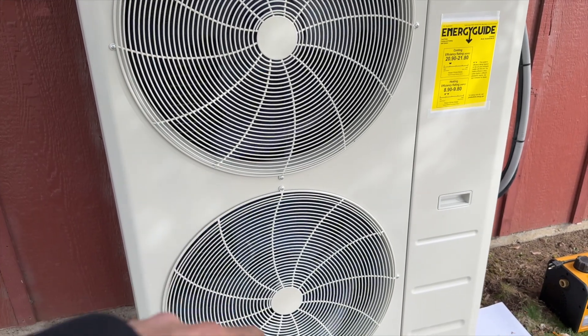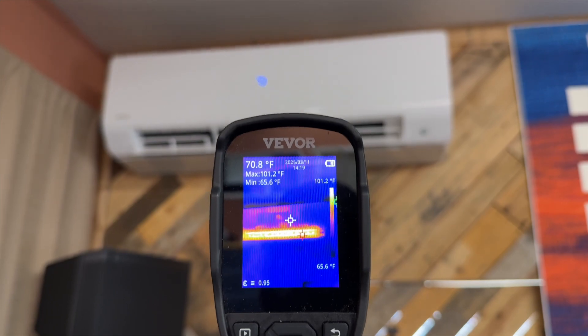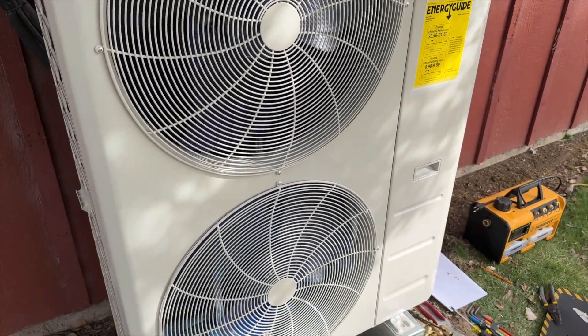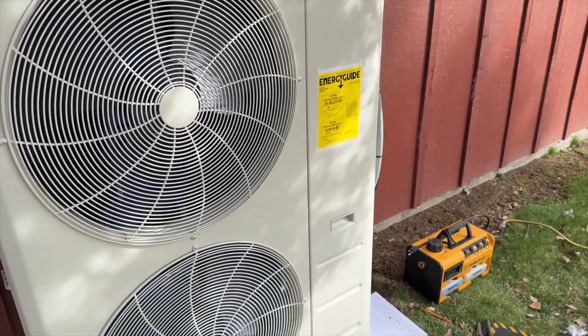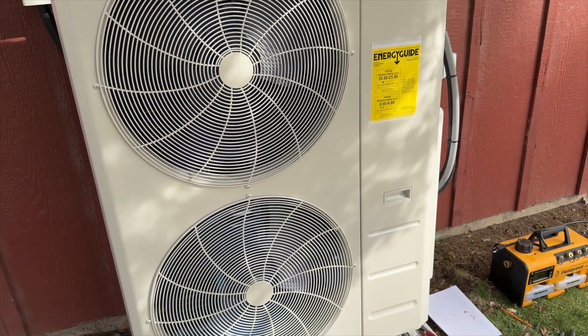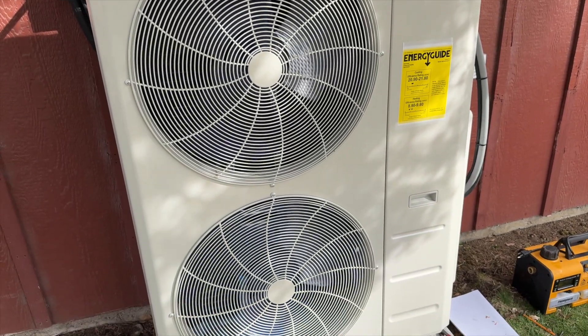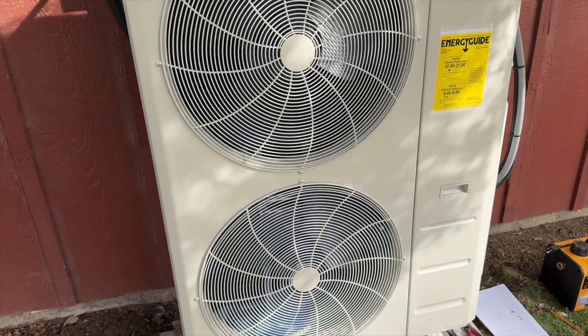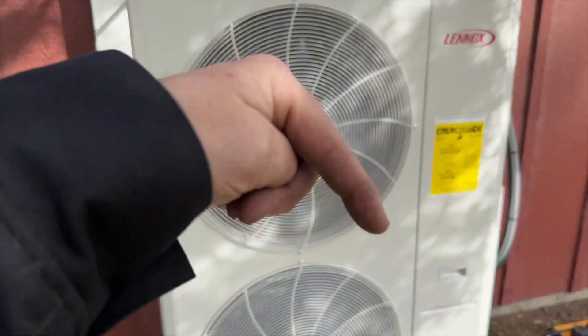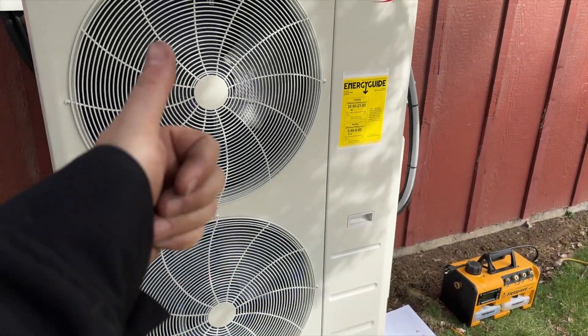She's running — both fans are spinning. Let's go inside and see what's going on. She is working. We got this one here at about 98 degrees and all three of them are working now. I couldn't show the last one because someone's working in there. So if you ever come across an F5 on a Lennox, be prepared — especially if it's under warranty, you're going to have to get a whole new unit. If it's not under warranty, you're going to have to sell them a new one, which is really unfortunate. Hopefully this helps. Thanks for watching — like, subscribe, hit the bell notification, and follow me on Instagram and Facebook.